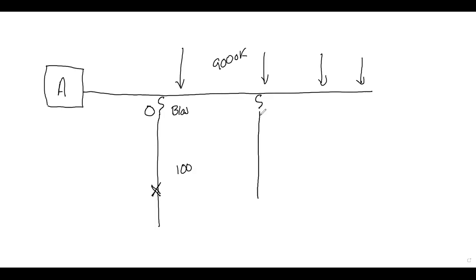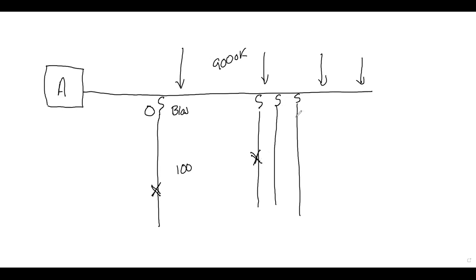When a single fuse blows, how many phases does it de-energize? One phase. If I have a three-phase tap line and there's a fault on one line, do all three phase fuses blow? No — it's only going to blow that one fuse. The other two phases remain on.